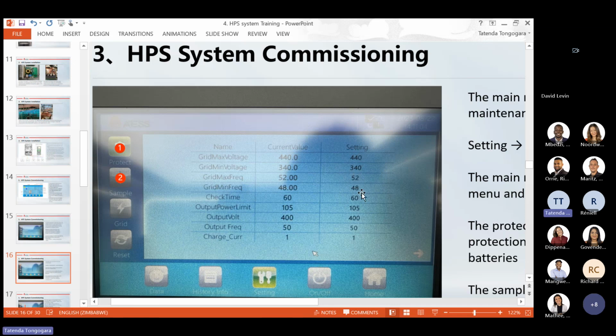For our frequency, 52 maximum and 48 minimum. So your frequency should not be above 52 or below 48. In the event that you're connected to a generator, your generator starts, but the HPS cannot accept the generator, it might give you an error of frequency too high or frequency too low. So what you need to do is maybe tune your generator so that its frequency, when it's on load, is within these parameters.